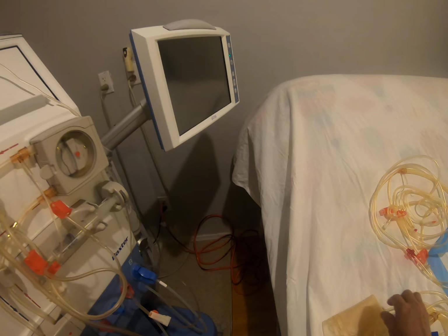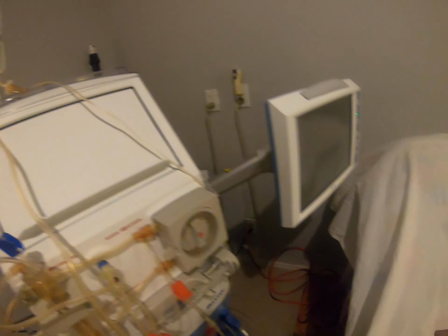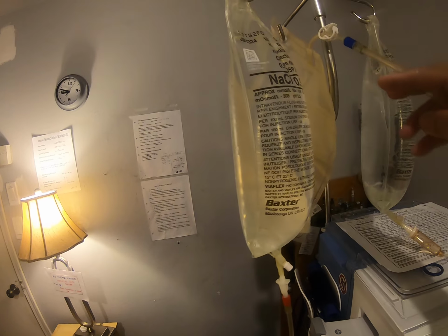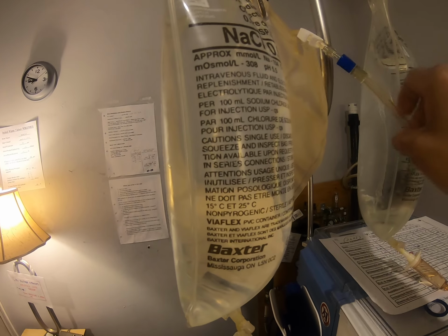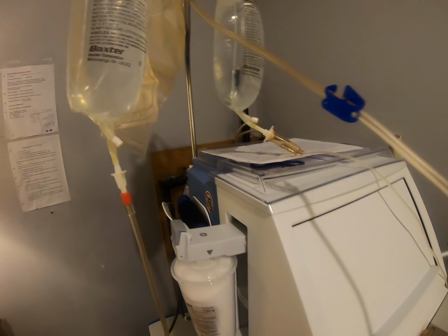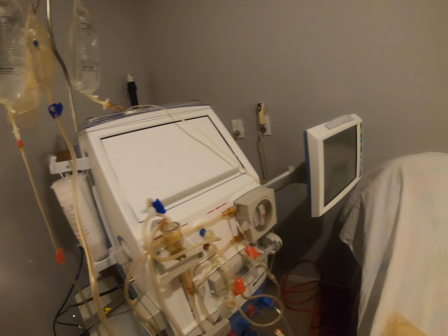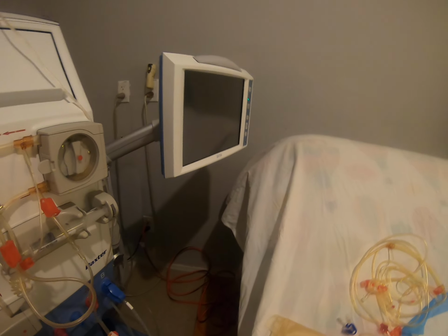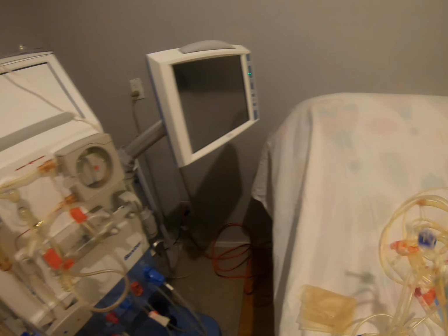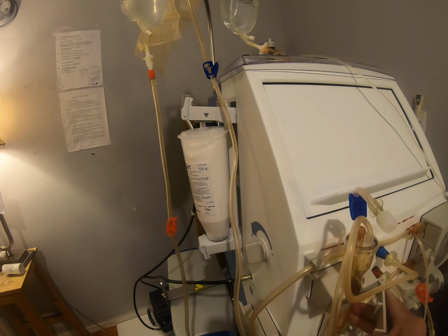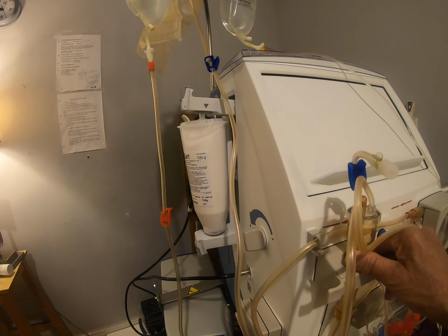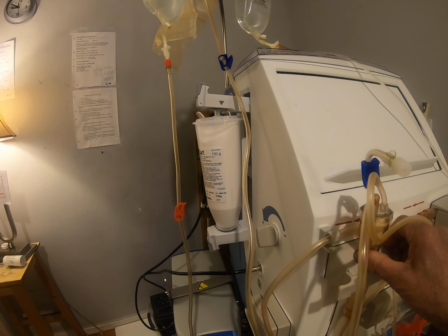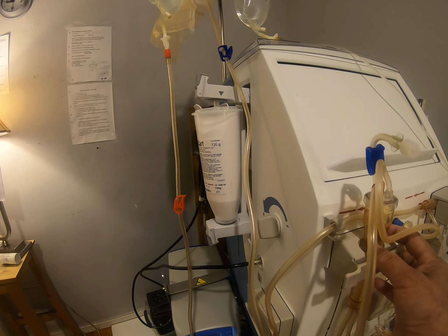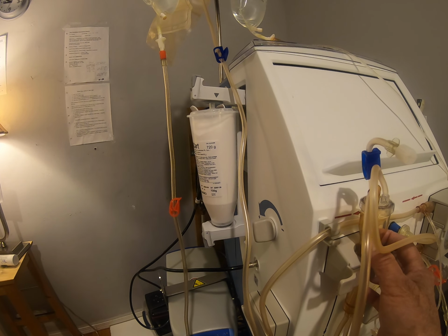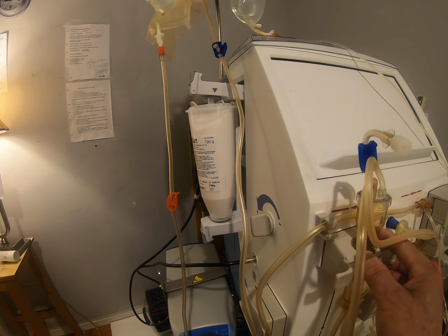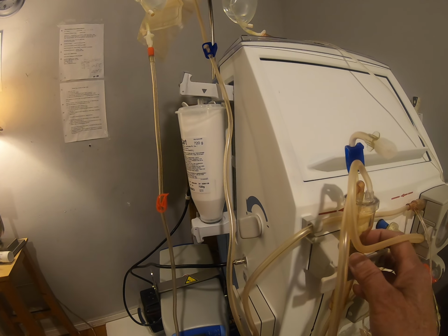So for the venous connection, you have a bag, and the bag we usually place upside down. We want it this way. The clamp is open. You trace this tubing, and you get to this chamber. You see this chamber here. It goes to the air detector, and it should be located this way, about a thumb size here. Be sure that when you fill this with normal saline later, the level is not too high and not too low, because we are trying to prevent air accumulation.